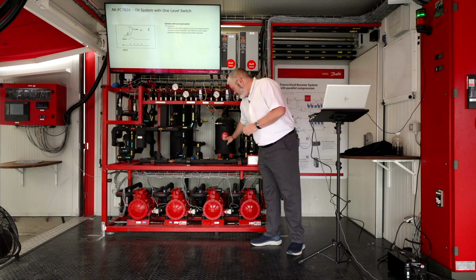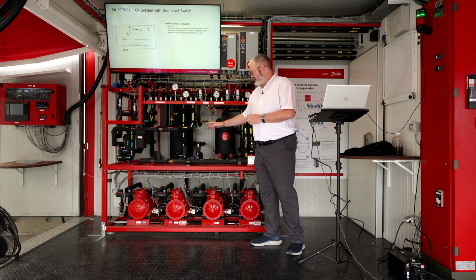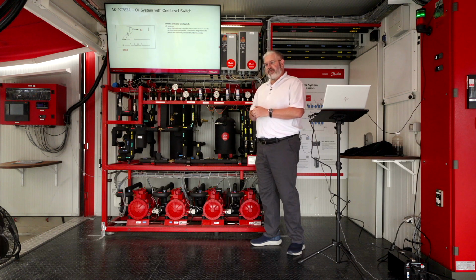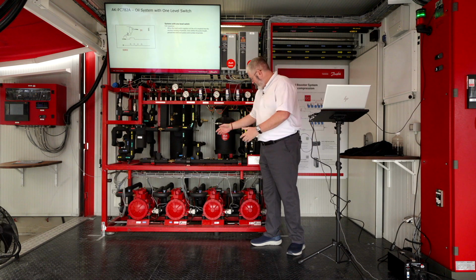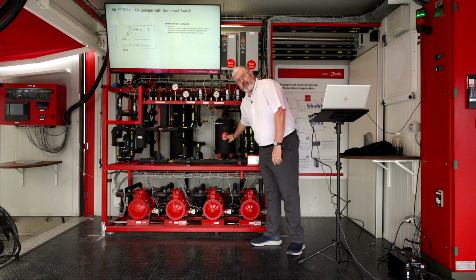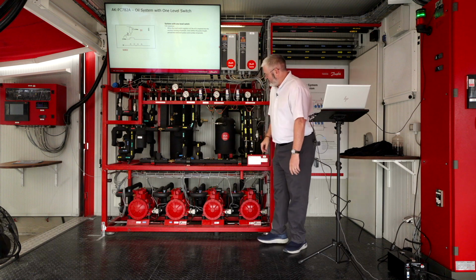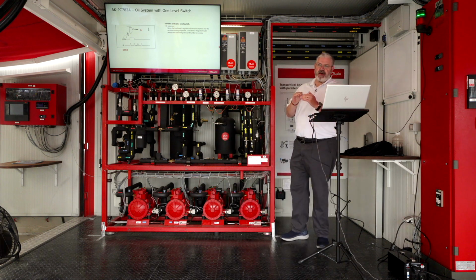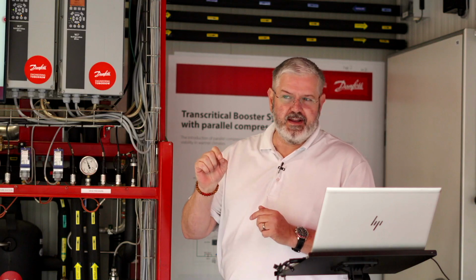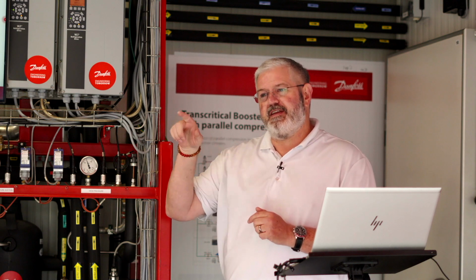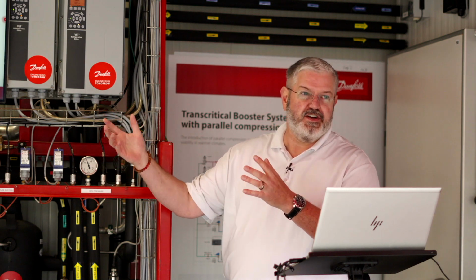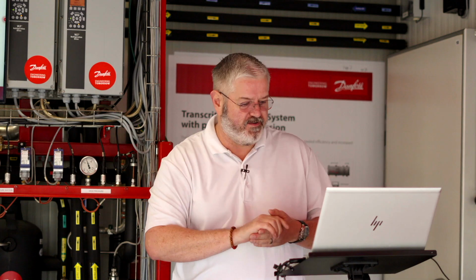So this oil reservoir is actually vented at flash tank pressure. So it's got a line that goes to the flash tank to stay at the same pressure. In our example, this is at 520 pounds pressure at all times because there's a line going over to the flash tank. So if you think about that venting over there, there's actually a little bit of load from that, that dumps into that medium temp suction that we don't show, but there is a little bit going over there as well.